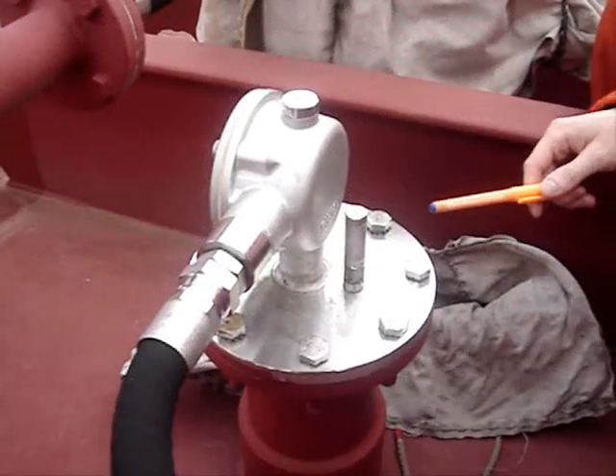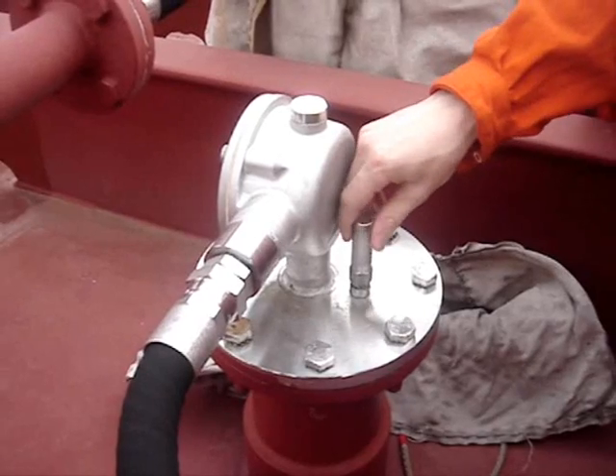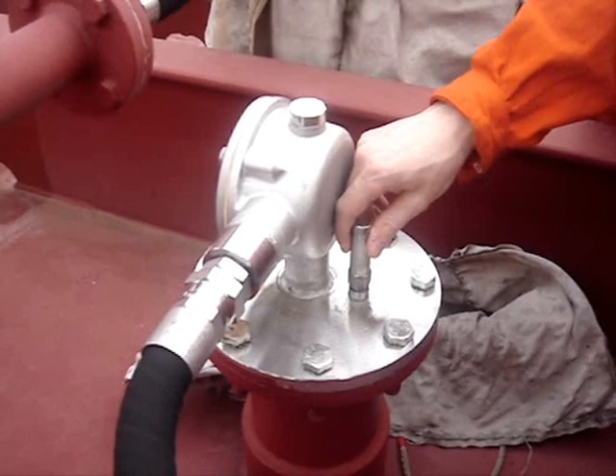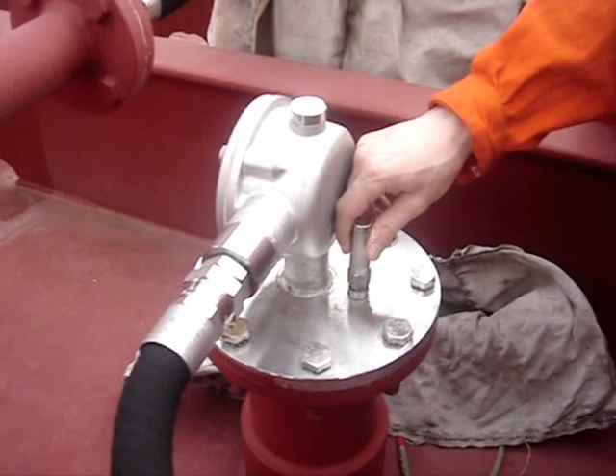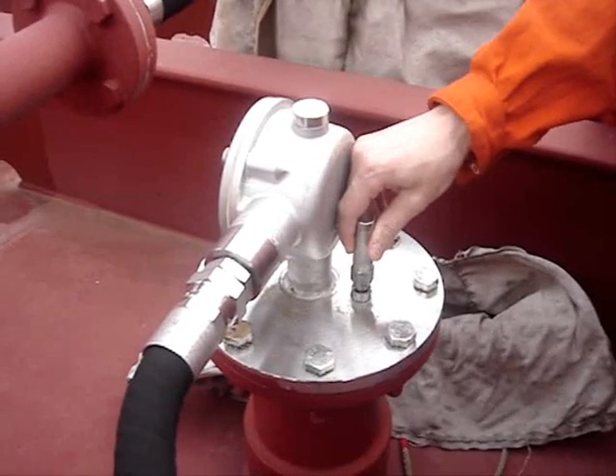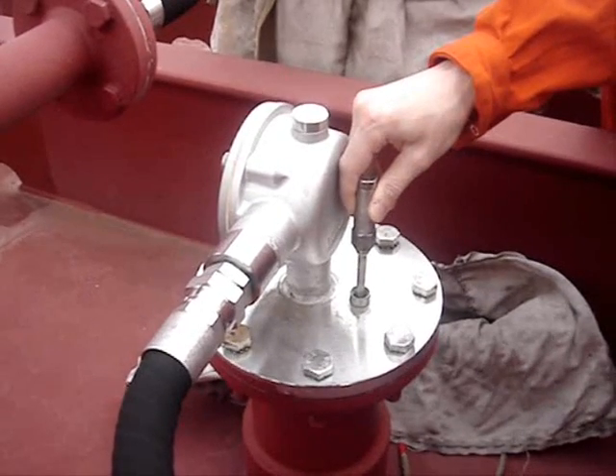To test the High Level and Overfill alarms we will need to unscrew the stick and start heaving it up. When we get one float disconnected from the reed sensor, the 95% alarm will sound with a delay of 2 seconds. When we get the second float disconnected from the reed sensor we will get the 98% alarm sounded, also with a delay of 2 seconds.